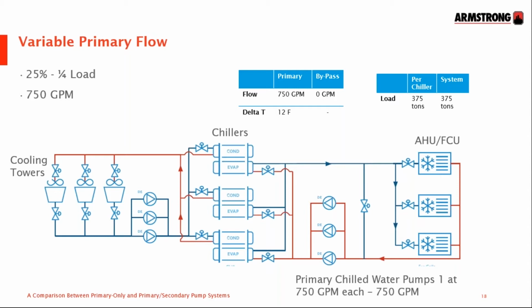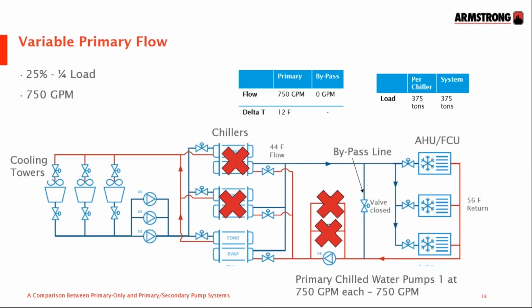The list goes on. For this example, we're looking at load-based sequencing, which is not the most efficient way of working. We've taken out two chillers, and we've got one chiller working at three-quarter load. So it's operating at a little bit better efficiency than it would have at full load, but we could have made it even more efficient by just having two chillers together at 37.5% each, and that would have optimized the efficiency better, assuming there was full chiller plant optimization in place. So we have a total of 750 GPM passing through the coils, and the chillers once again run to that fixed delta T of 44 out, 56 coming back.